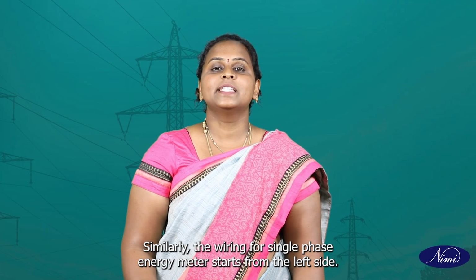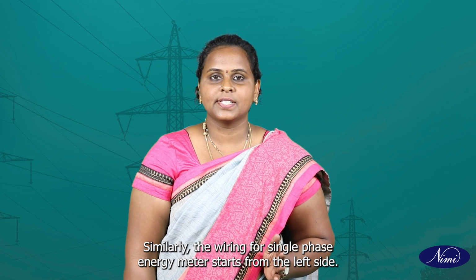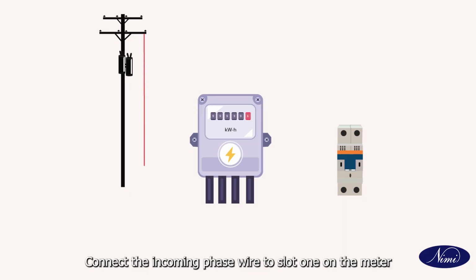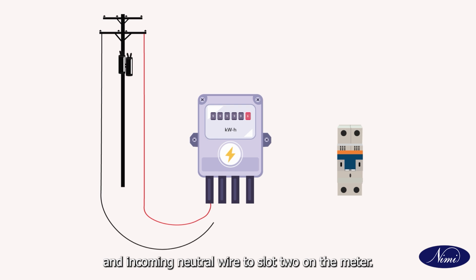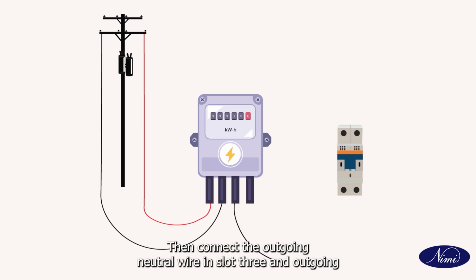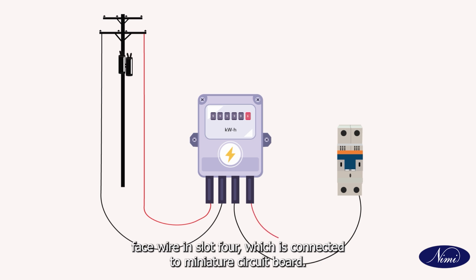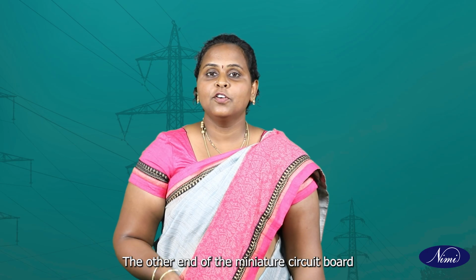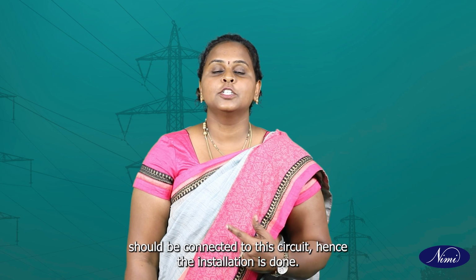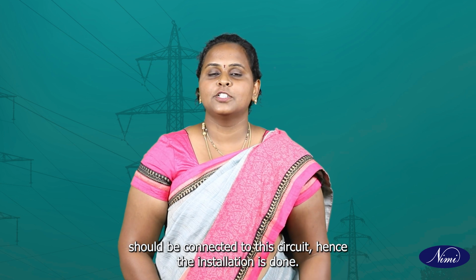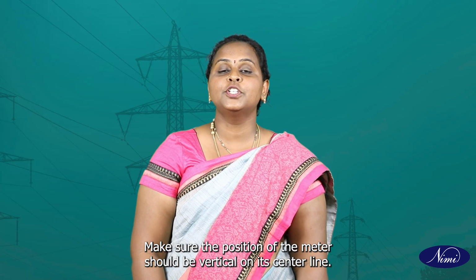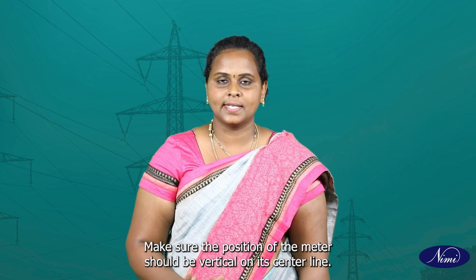Similarly, the wiring for single phase energy meter starts from the left side. Connect the incoming phase wire to slot 1 on the meter and incoming neutral wire to slot 2 on the meter. Then connect the outgoing neutral wire in slot 3 and outgoing phase wire in slot 4, which is connected to miniature circuit breaker. The other end of the miniature circuit breaker should be connected to the circuit, hence the installation is done. Make sure the position of the meter is vertical on its center line.